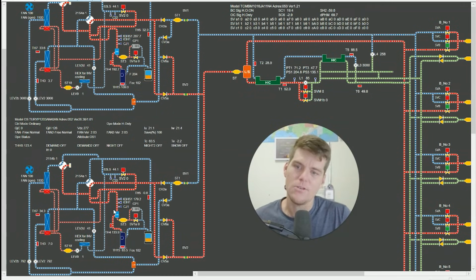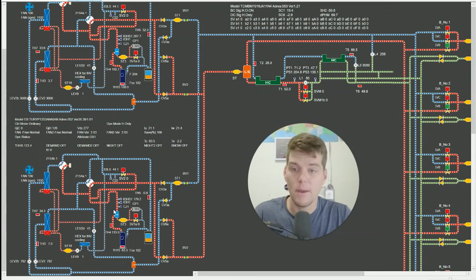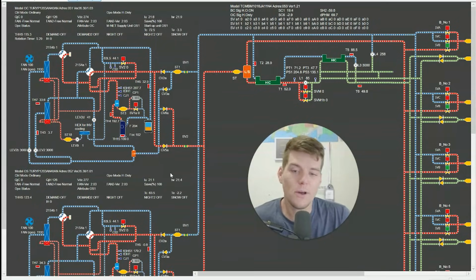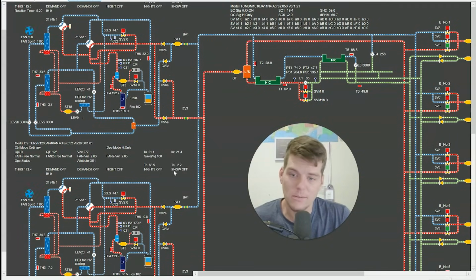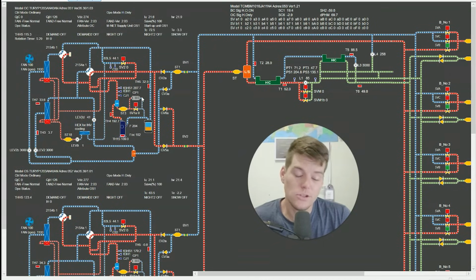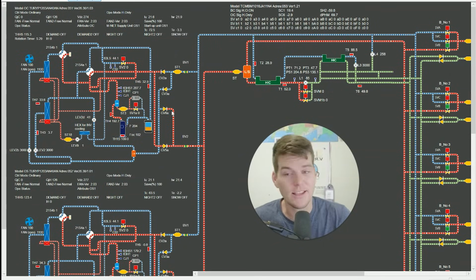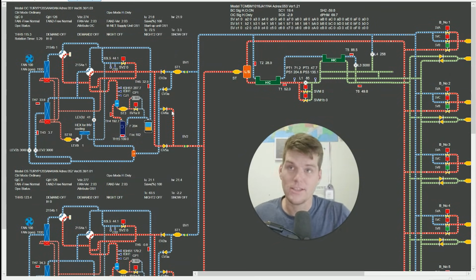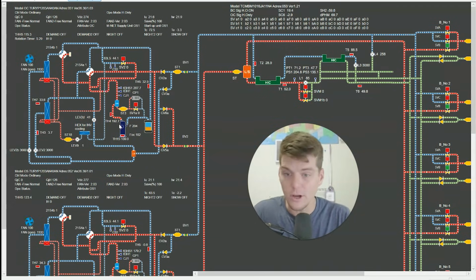So lack of heating. Okay, so where's my mind going to go? Maybe it's going to go to charge. Well, what do we know about the troubleshooting triangle that I've been teaching about and talking about for almost 3 years now? Well, we know that we can check what? Discharge superheat, suction superheat, system subcooling. That's not specific to Daikin. That's universal for all refrigeration equipment. So let's look at that, right?